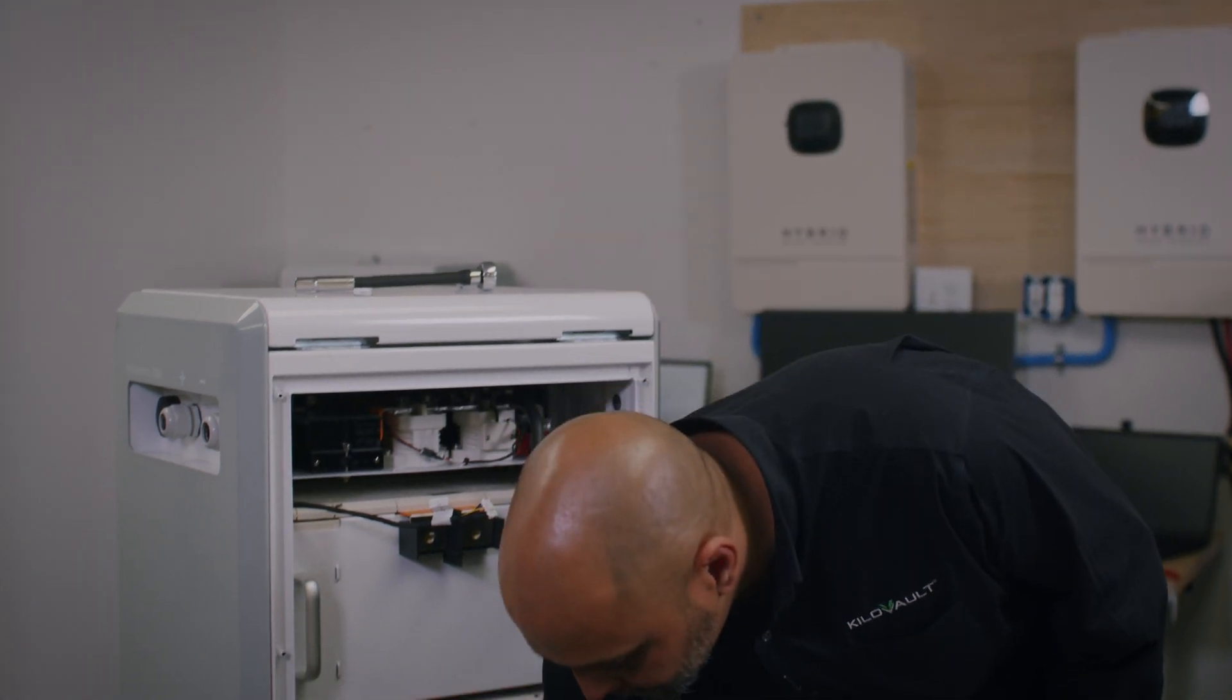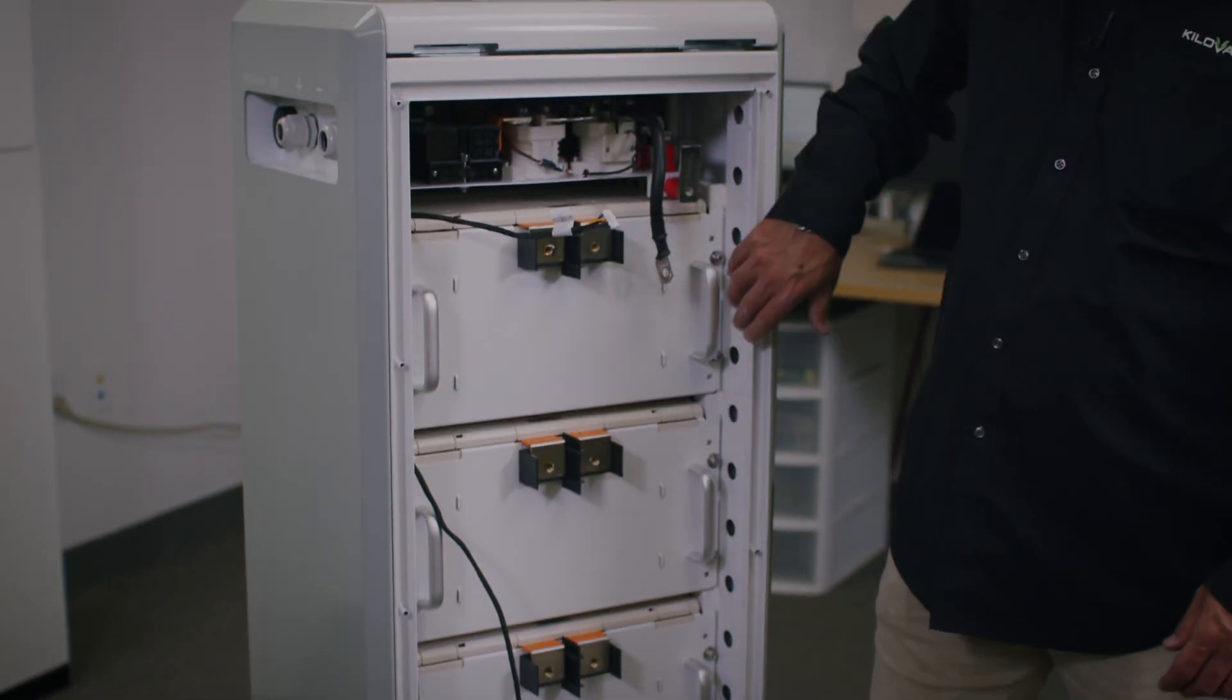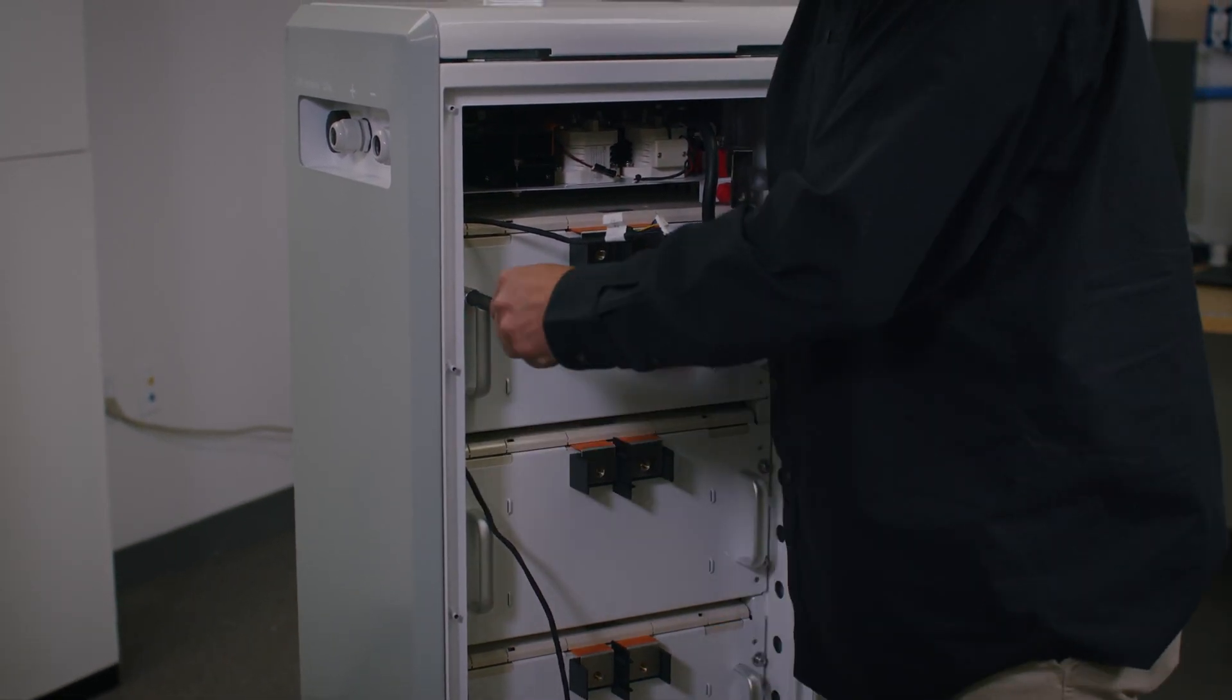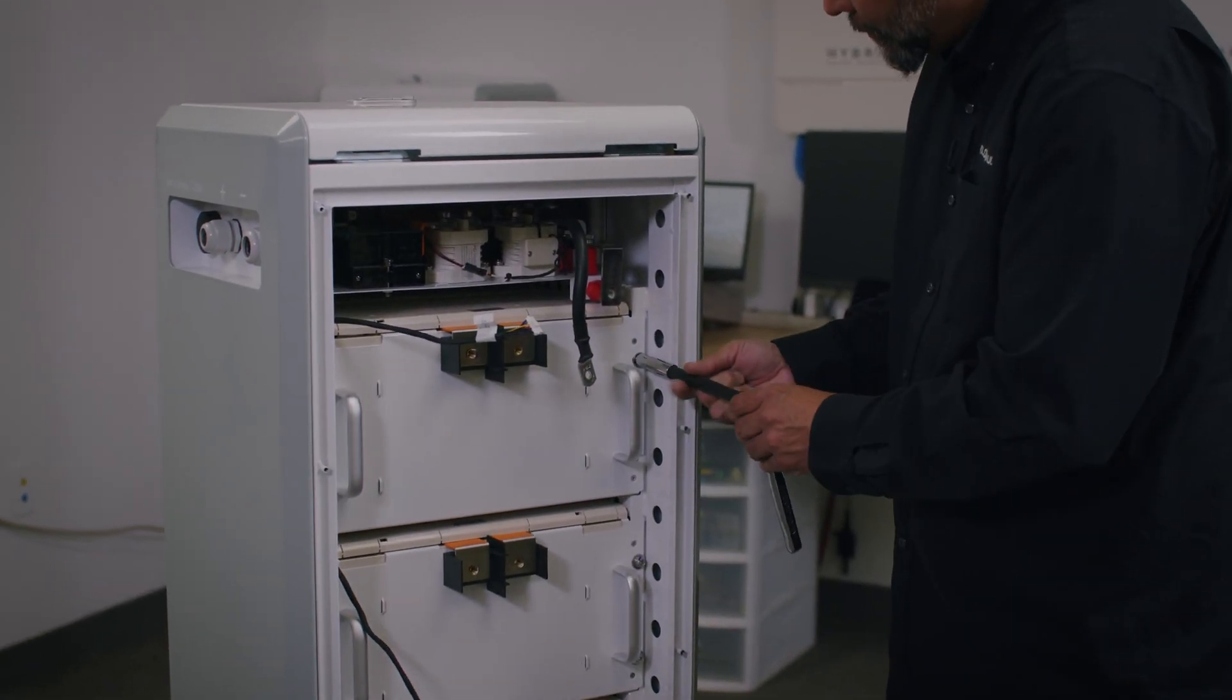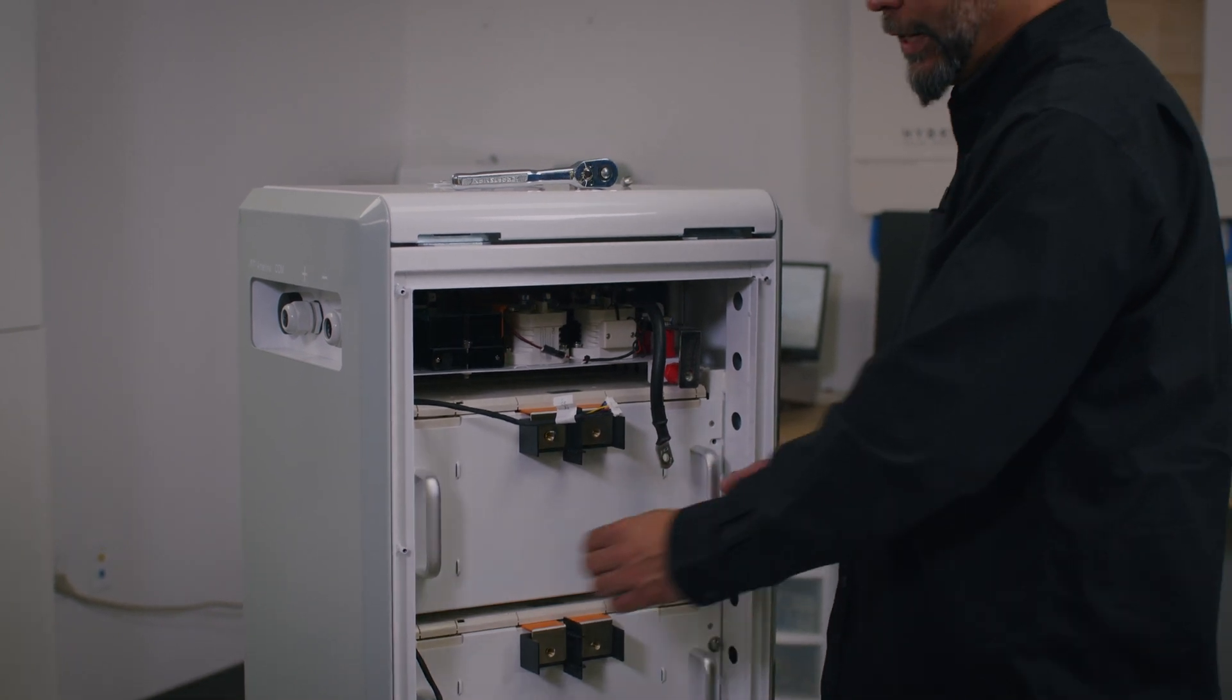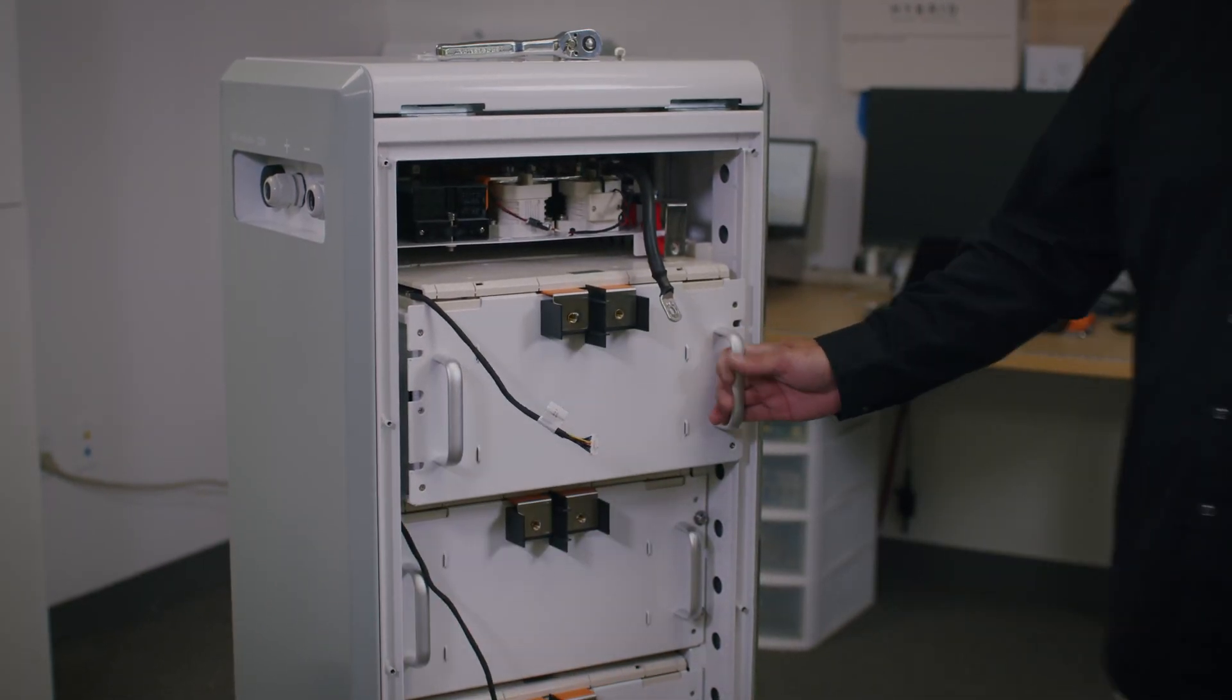Now that we have disconnected all the modules from the BMS and the cables should look like this, let's go ahead and unbolt the four bolts that hold down each module and they will be ready to be removed. Now that all four bolts have been removed, the module just slides out, making it easy to remove from the actual bank.